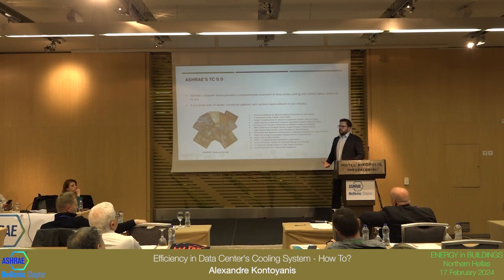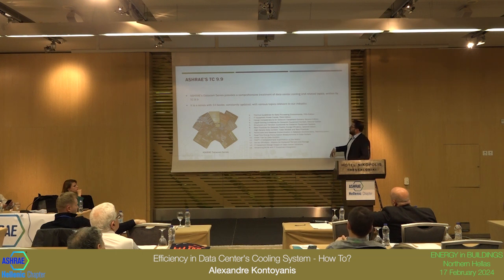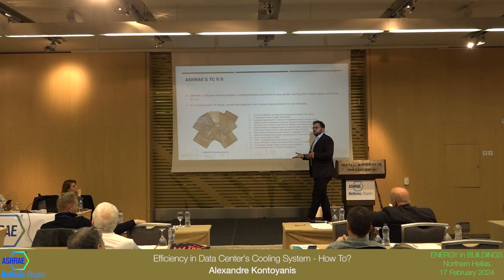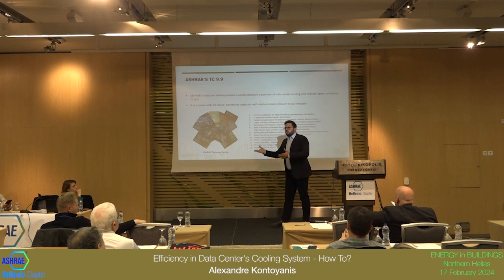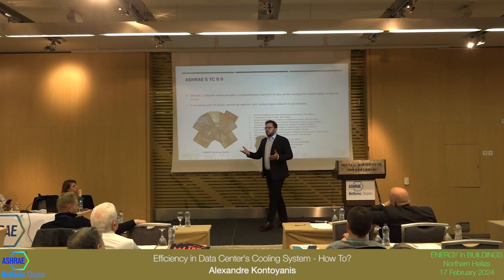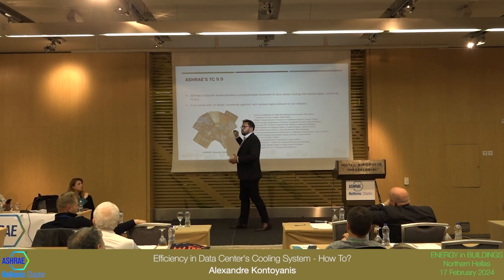You can see some racks consuming 300 kilowatts in a space like this. It's just too much heat. The only way to cool is by liquid. Well, it's an opportunity. TC 9.9, you can join us. You don't have to be a member of ASHRAE to join a TC. Of course, you should be a member of ASHRAE, but you do not need to be. You just go to the ASHRAE website and join a TC.